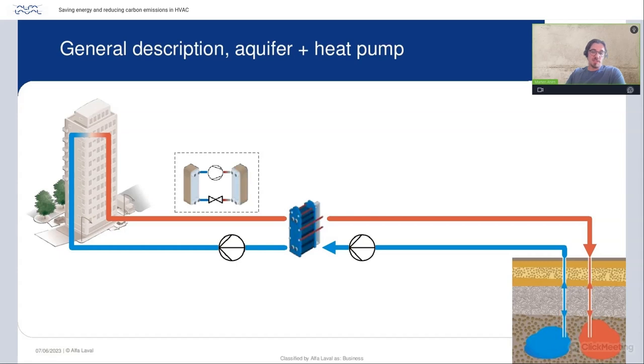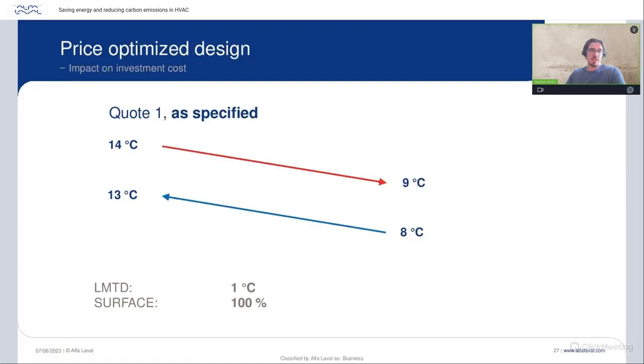So if we look into this specification as it was written in the market, this is what was specified by the consultant. We talk about LMTD, the average temperature difference between the hot and cold side. As you see, it's 1 degree on the cold side and 1 degree on the hot side. So the average temperature difference between the hot and the cold is 1 degree. When anybody makes a design, we use that as a reference. To perform this duty, we need 100% surface area. But what about the market tolerances that have been applied in the market?